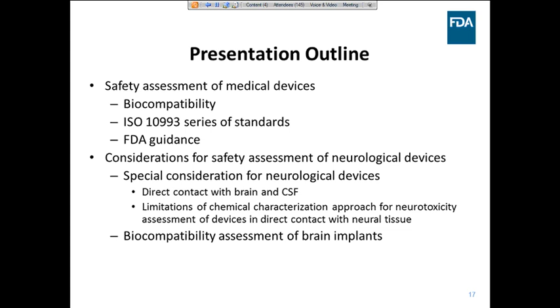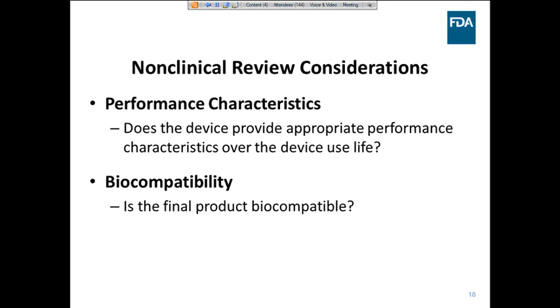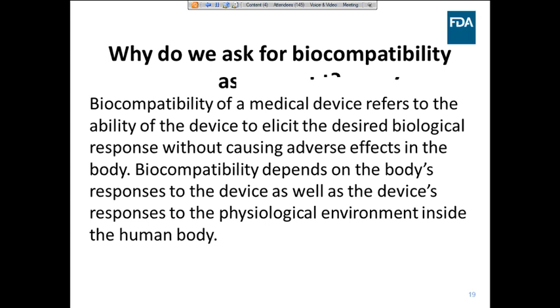So there are 2 important considerations for non-clinical review of medical devices. One is performance. The question is, is the device going to perform as intended? The other one is about safety. Is the final product going to be biocompatible? For today's talk, I will focus on the biocompatibility assessment. So what is biocompatibility? Biocompatibility of a medical device refers to the ability of the device to elicit the desired biological response without causing harm in the body. So it depends on the body's response to the device as well as device response to the physiological environment inside the human body.